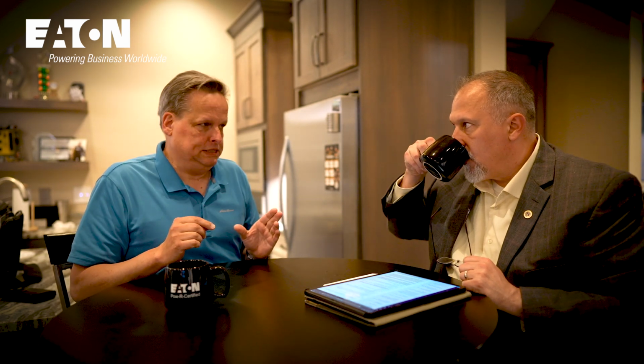But really, when you think about the requirements of receptacle placement, as I walk through that door, if this is a required receptacle, and it's a room, not a hallway, for example, I don't need a receptacle until I'm 6 feet away from that doorway anyway. So the only thing I need to do is probably move that receptacle over one more stud bay or something like that, and GFCI protection would no longer be needed. So it's just with a little careful planning, yes. But here's my problem.